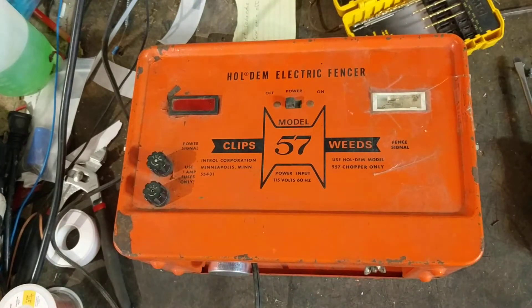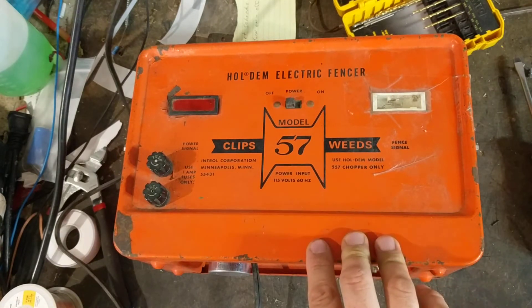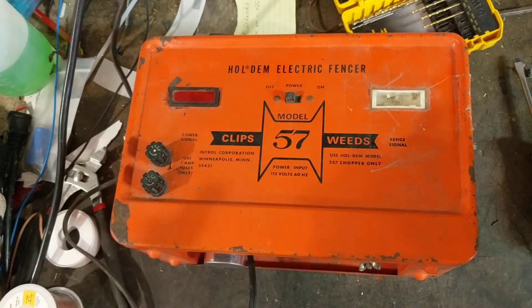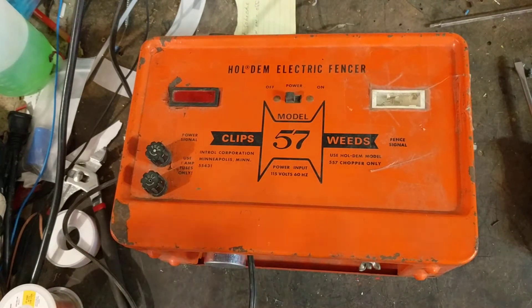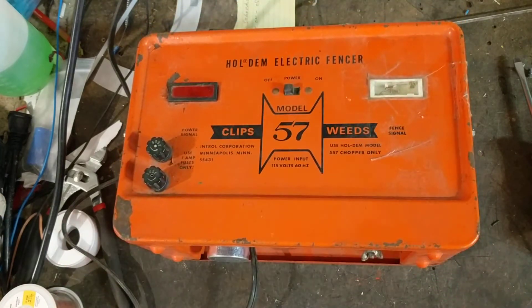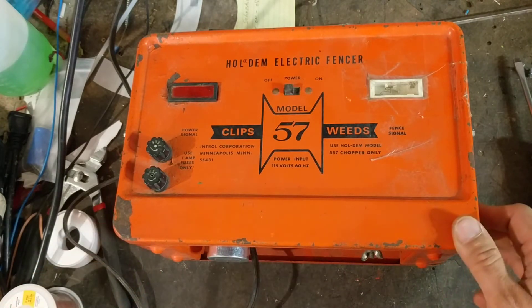This is one that we fixed for a customer. He said he could only get a couple volts out of it. I'm not sure how he was testing it, because you can't use a standard electric fence tester on these things — they put out a different type of shock voltage. I don't want to risk messing up my meter, so I don't test these with a voltmeter. I just use a short piece of wire or a screwdriver across the terminals.